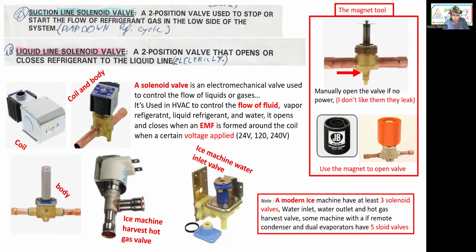A solenoid valve is an electromechanical device used to control the flow of liquids and gases. It's used in HVAC to control the flow of fluid, vapor refrigerant, liquid refrigerant, and water. It opens and closes when an electromagnetic field, which I covered when I did Ohm's law, is formed around the coil when a certain voltage is applied. It's either 24 volt, 120 volt, or 240 volt. We have the coil, which you can replace with whichever voltage you want, and we have the body. We also have the hot gas valve. The teacher, when I was in school, didn't mention it back then. It's used very much on ice machines, with hot gas harvest. Harvest is for the ice to drop. And we also have water inlet valves used on ice machines. And on top, we also have a magnet tool.